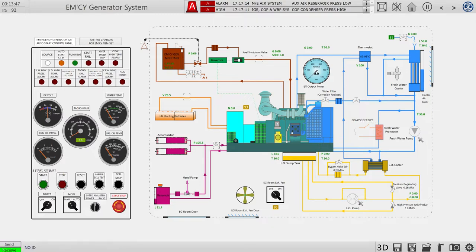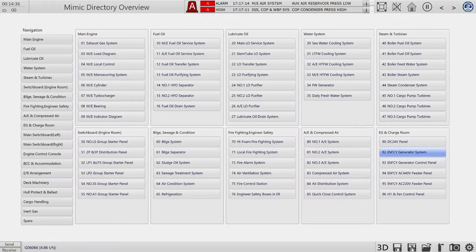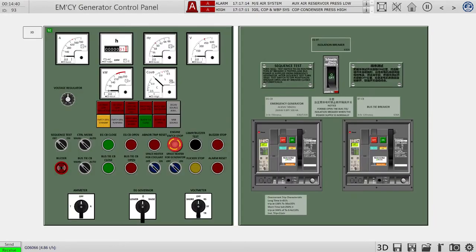Let's press the start button — our generator is running with the batteries. After confirming everything is fine, we can see the water temperature, lubricant pressure, and rotor temperature, which is still low. In about five minutes it will be hot enough. After verifying everything is fine, I will set it to automatic mode and go to the control panel.